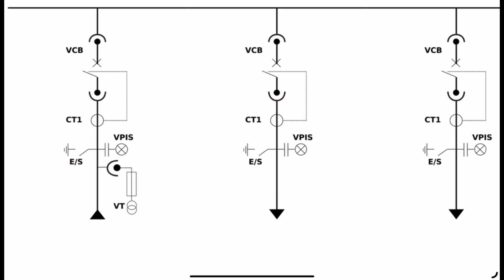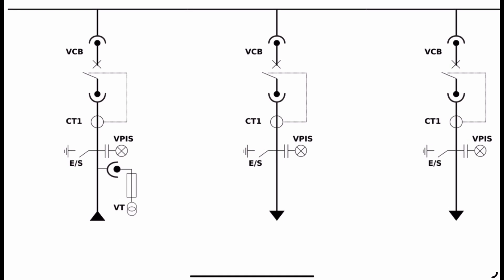Moving further, we have a circuit breaker. This symbol represents the circuit breaker, and it is a Vacuum Circuit Breaker — written as VCB — which is most commonly used in medium voltage switchgear. If you're interested in learning more about vacuum circuit breakers, I have a dedicated playlist linked in the description. This VCB, if you notice, is again wrapped in a bracket symbol, meaning it is a withdrawable-type circuit breaker.